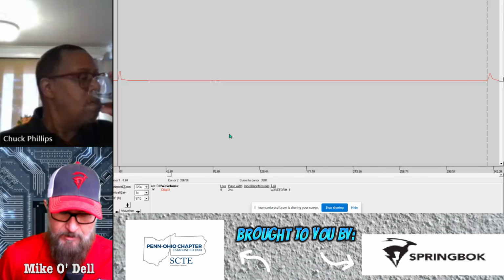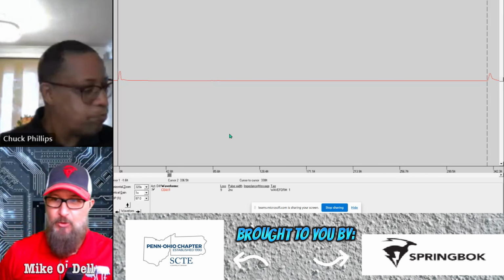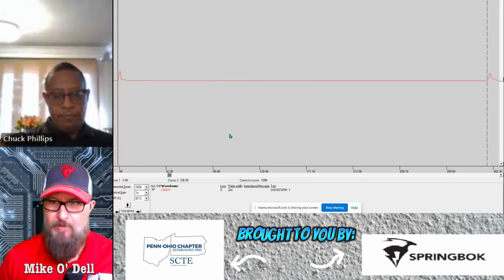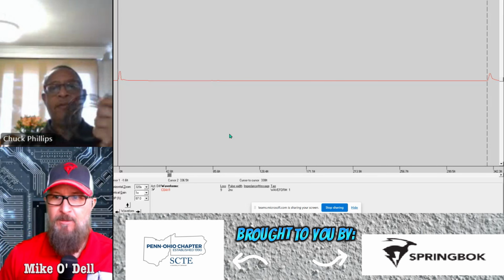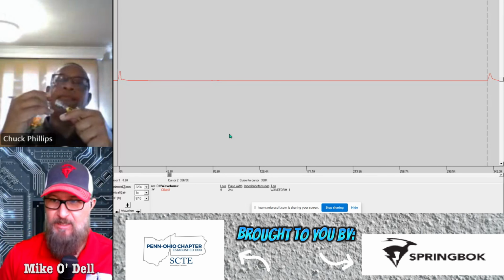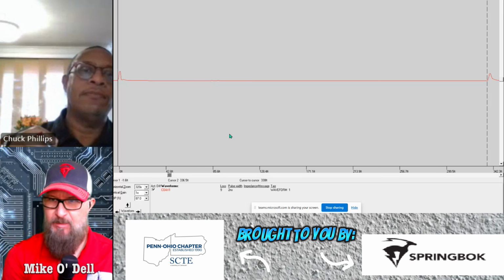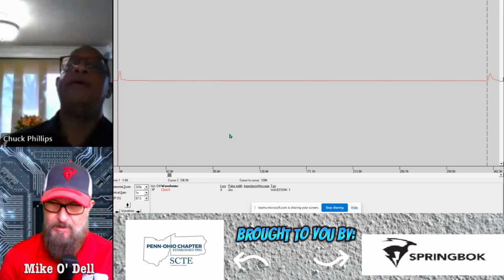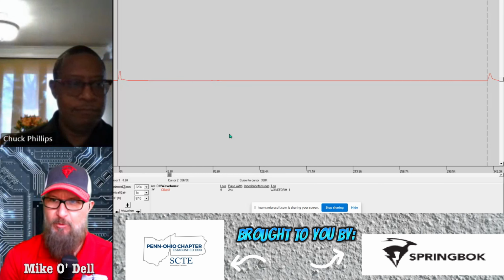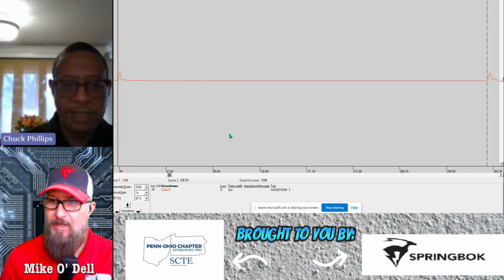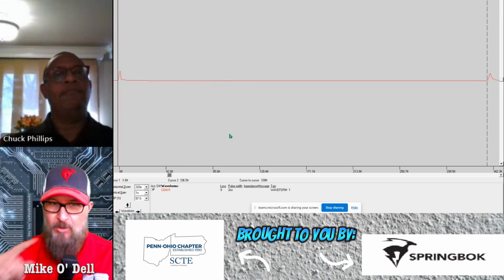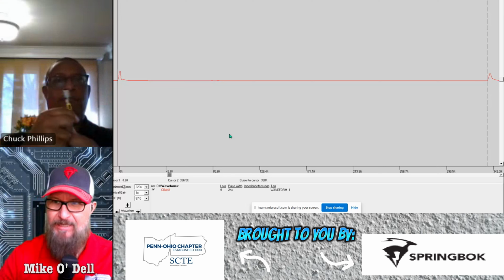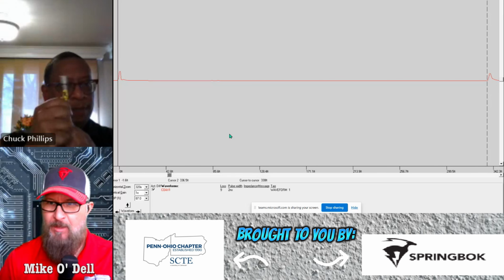So the way I learned was to take your launch cable or your jumper cable, connect it to your TDR, with the velocity of propagation for the cable that's going to be under test. And in most of my cases, it's been distribution feeder trunk cable, 87-ish. You'll have an open on your TDR trace at the end of your launch cable.